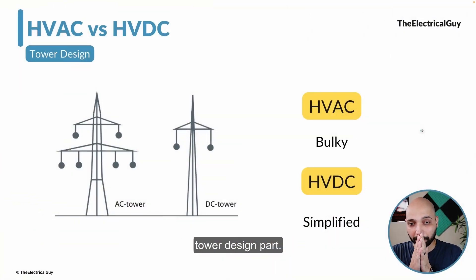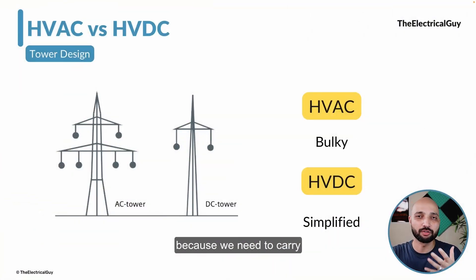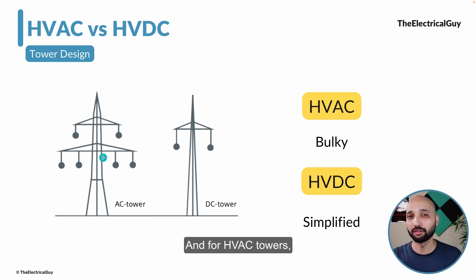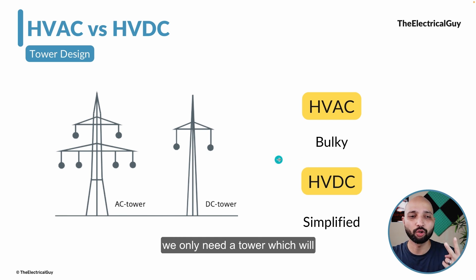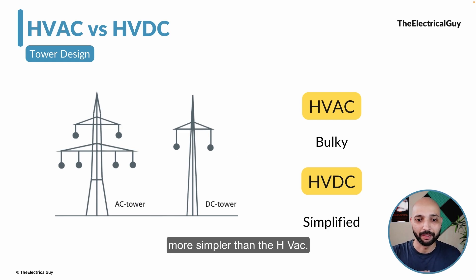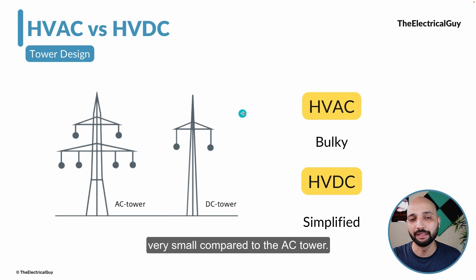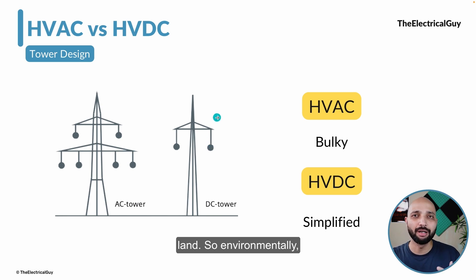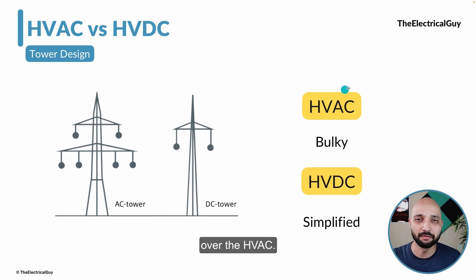Moving on to tower design. The HVAC tower is bulky because it needs to carry three conductors — as you can see on the left, a double circuit tower design requires a significant amount of steel. In contrast, the HVDC tower only needs to carry two conductors, making the design much simpler. The footprint — the land required — is also much smaller compared to the AC tower. This adds to the environmental advantage of HVDC: it uses less steel and less land.